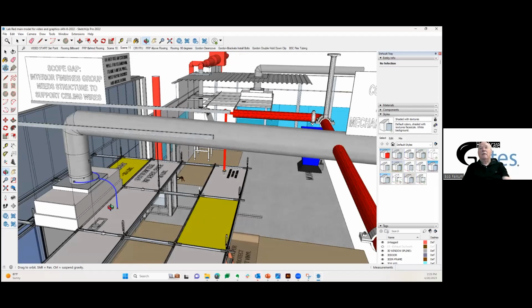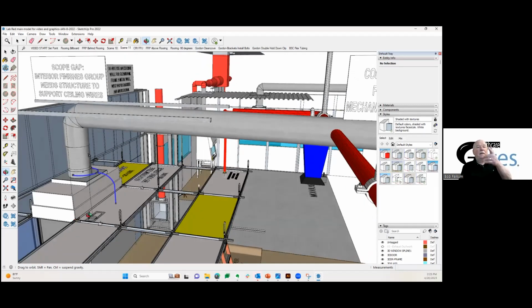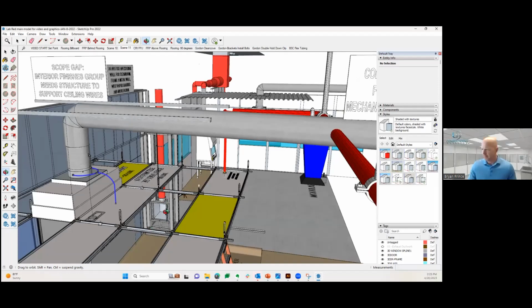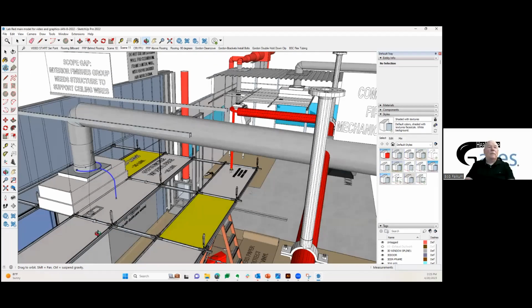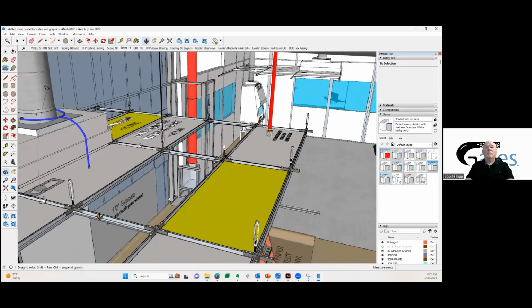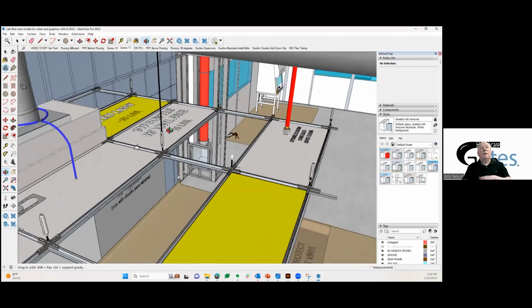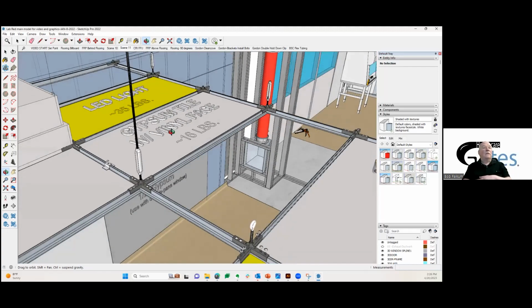It's sacred. Now back to the ceiling — you can leave it the way it is. This is not a grid system, it's actually a support system. The purpose is putting in a uniform, very strong grid that doesn't move, because it'll leak. You're either positive pressure or negative pressure, but you want to avoid leaks as much as possible. The ceiling tiles themselves should be vinyl coated and seamless. You'll notice these are very strong turnbuckles and so forth to walk on it — again, you don't walk on it, but the point is, it works.